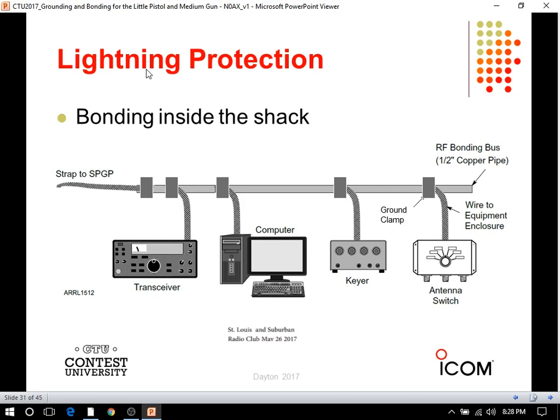This drawing, a variation of it, has been in the handbook for years. Basically you get a big piece of half-inch copper pipe, the right kind of ground clamps, and run a wire to everything in the shack - your radio, computer, keyer, antenna switch, even if it doesn't have power going to it. This goes to your single point grounding panel, which also goes to your AC safety ground. Everything is bonded together now. You've done one bonding operation and solved 3 problems - that's important, you save money and get the job done right. That's what it looks like.